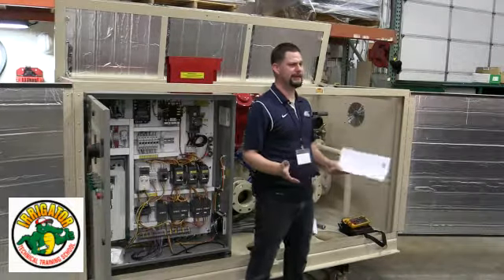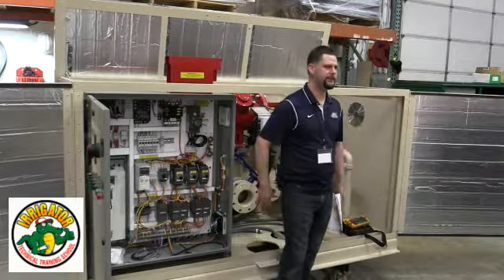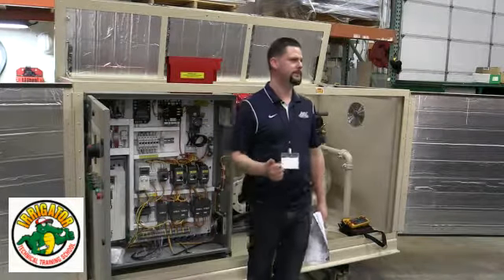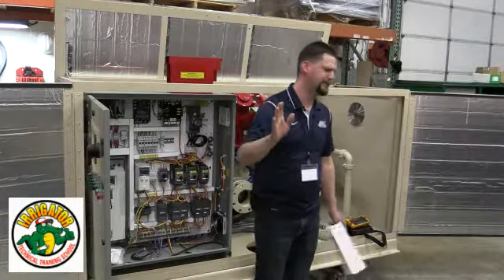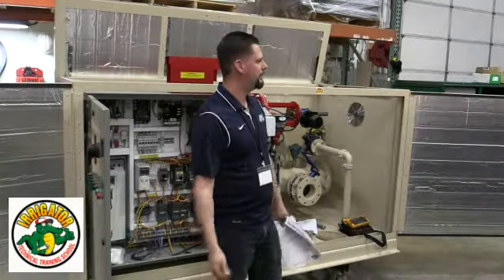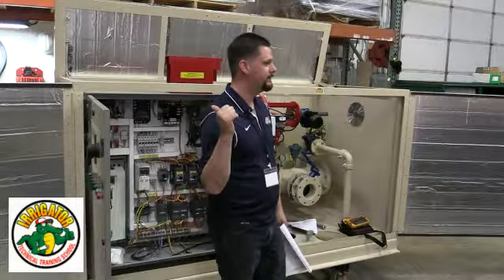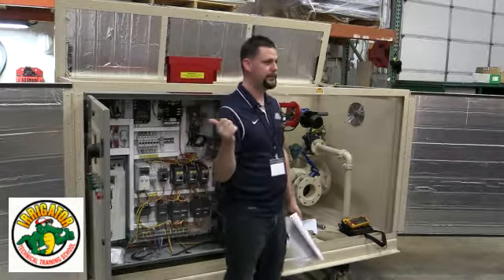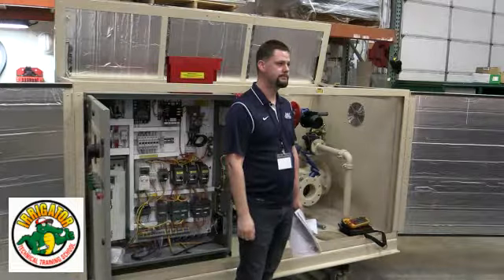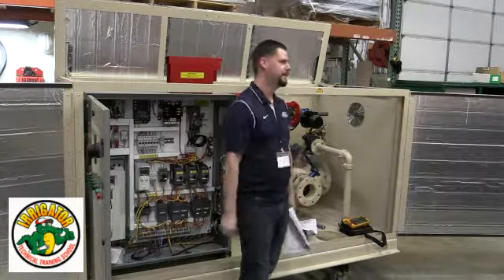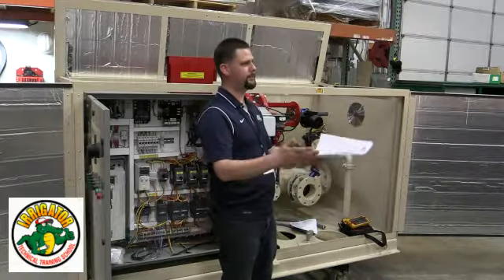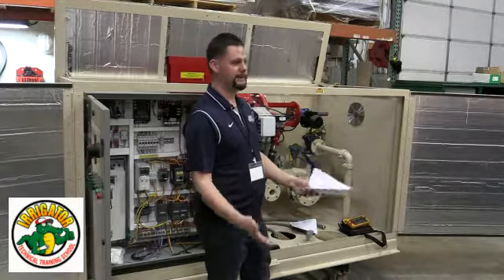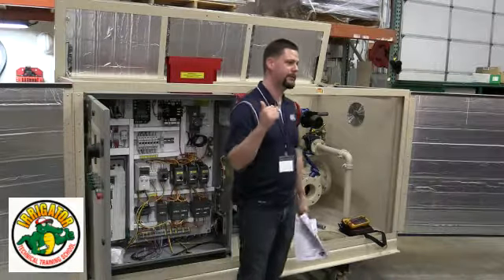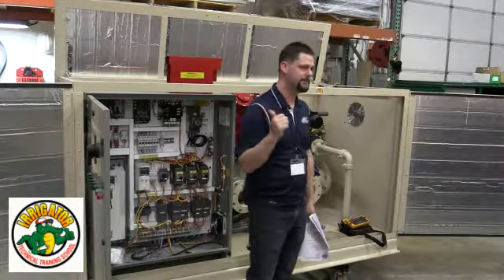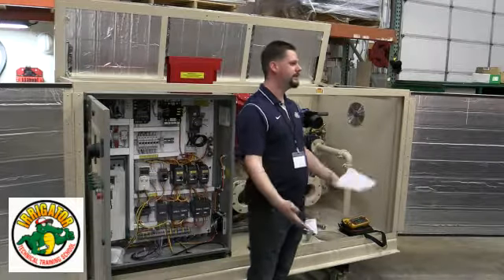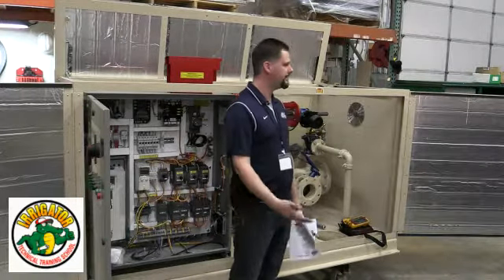So this is how we compromised. During normal operation, they were pumping about 120 gallons per minute for their whole city. There's like 400 people in this small town. So it was, all right, with this flow, let's run 1 pump full speed and see what it does. We'd pick a pump, and if it got too high, we'd turn it off. We found 1 pump that was a little bit higher pressure but maintained their flow. So if you lose analog signal, I had the program patch downloaded by the time we were done with the conversation. But that's the type of thing that needs to be addressed during a startup.